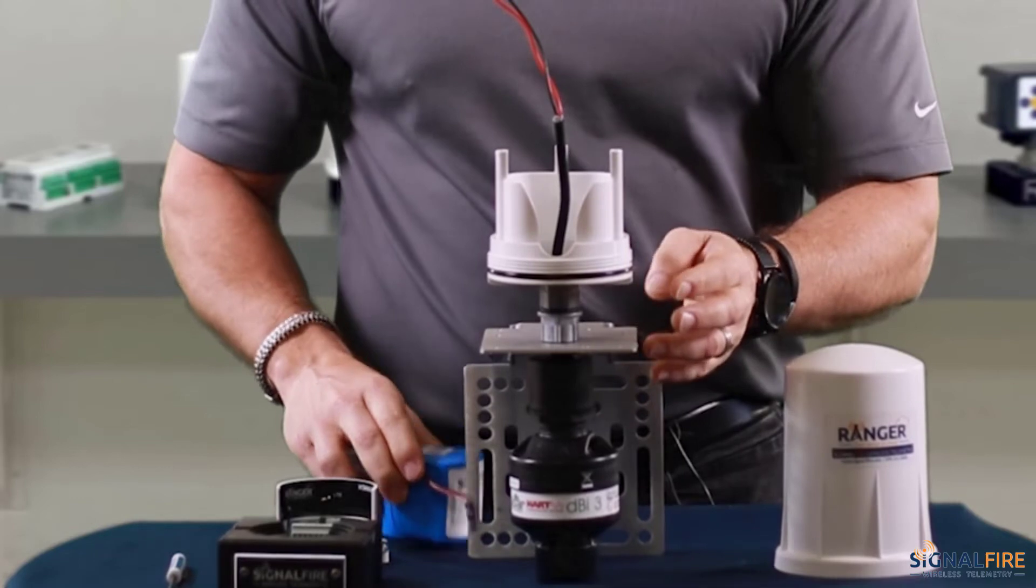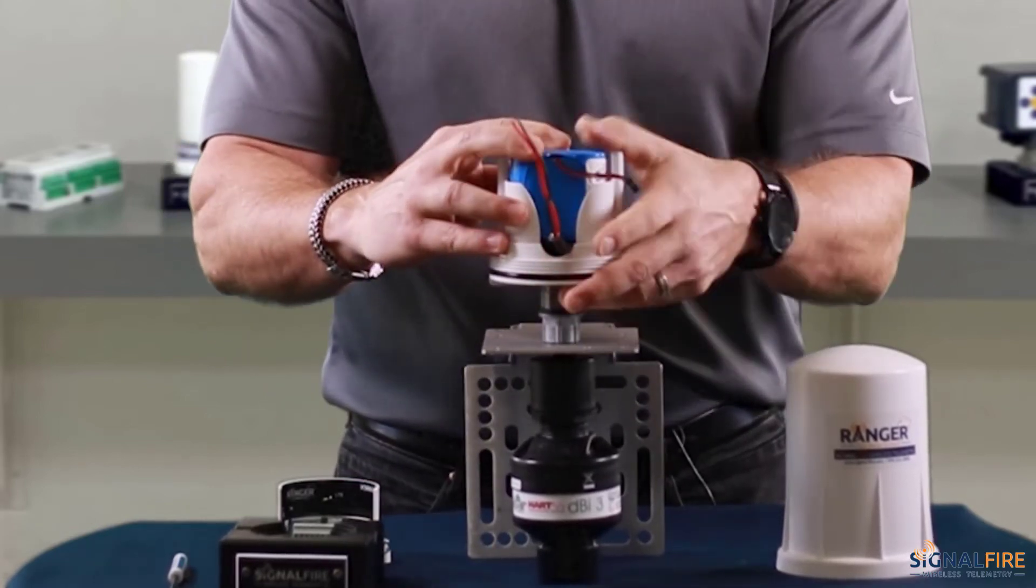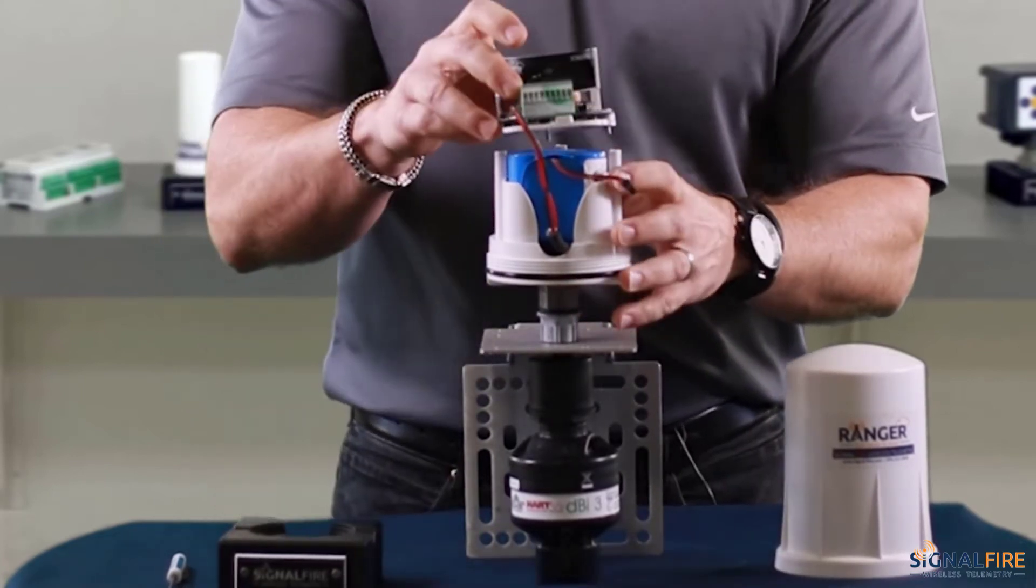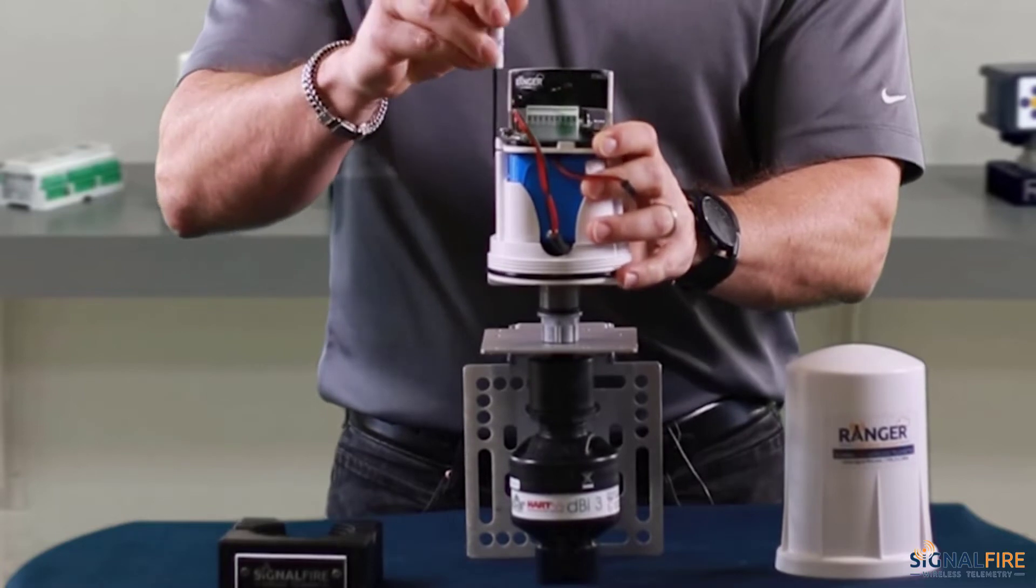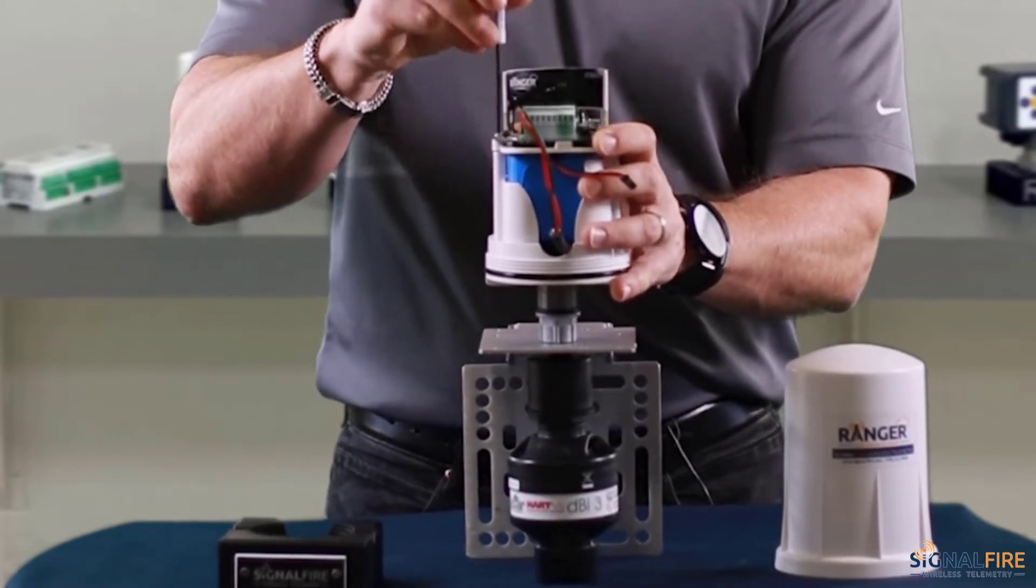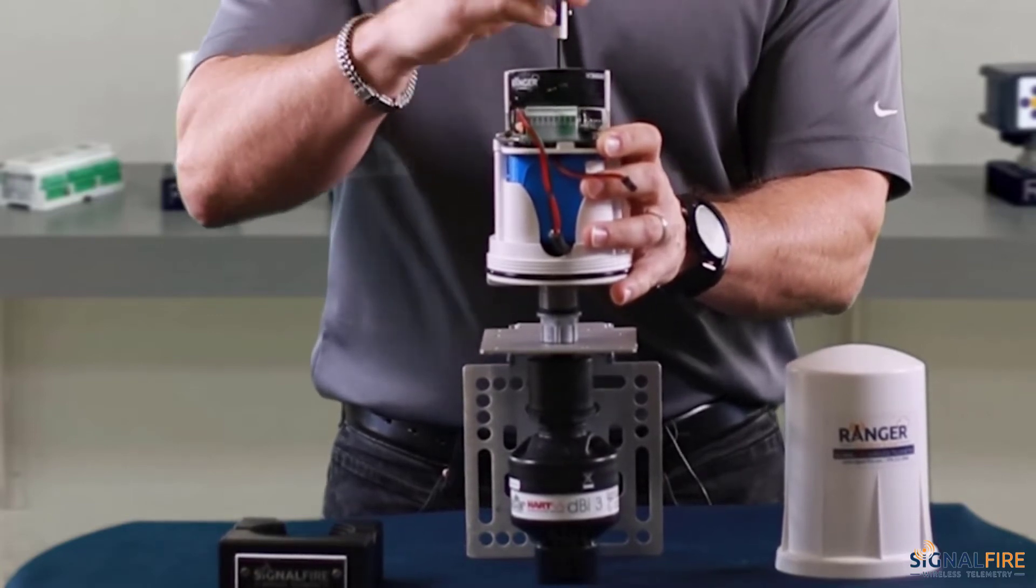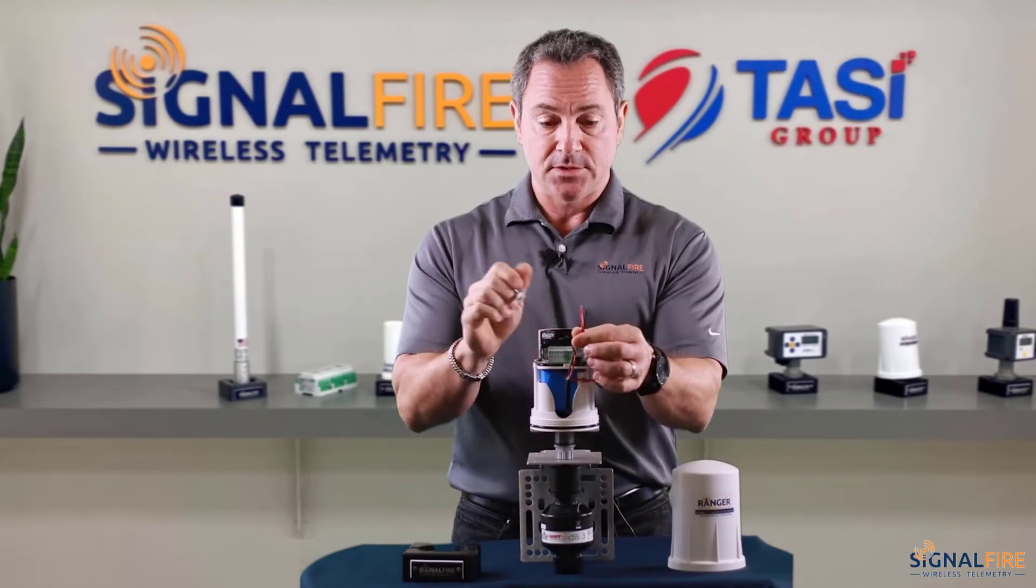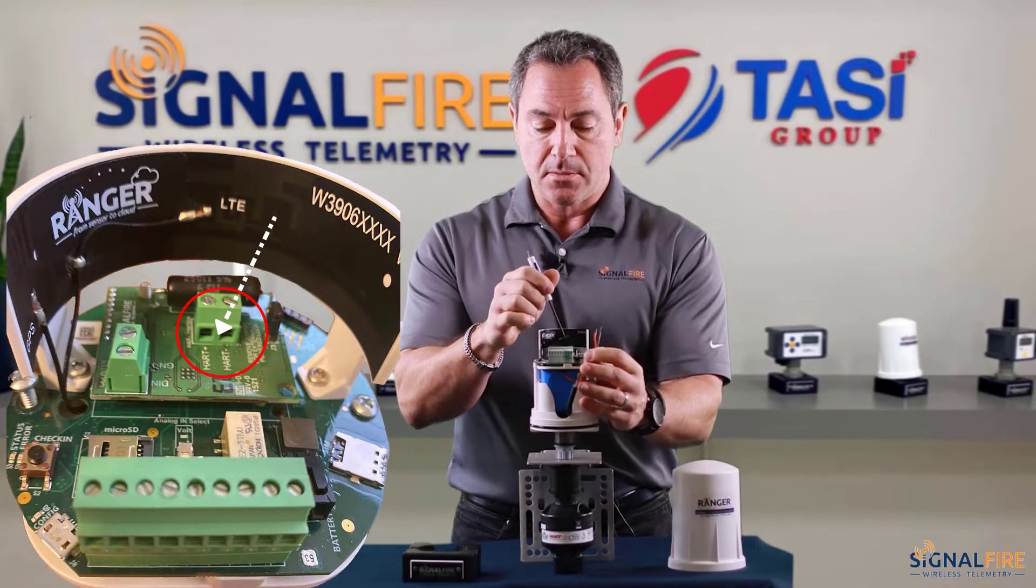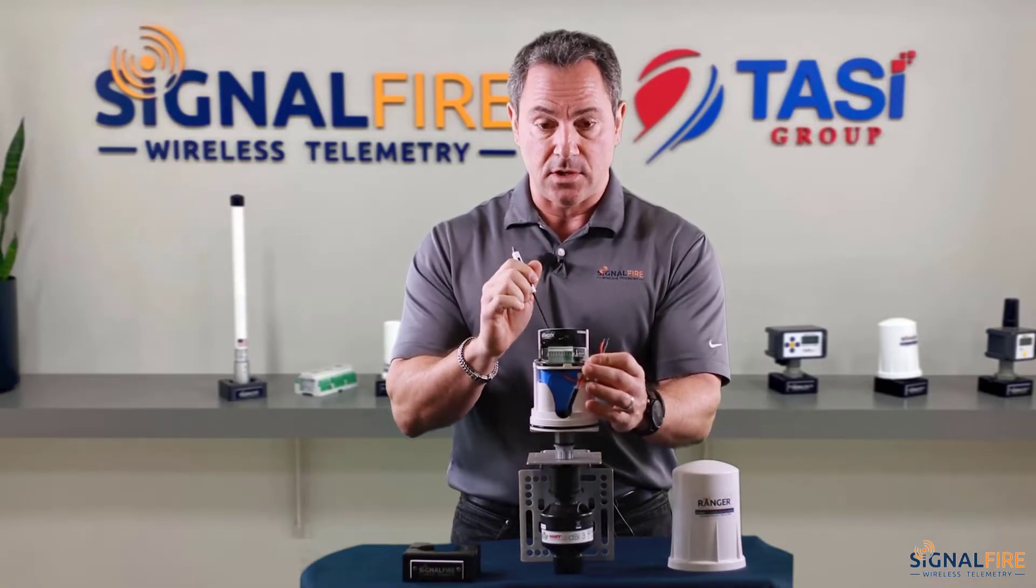And finally, let's reassemble the tower, put everything on top of it. Let's put the battery, then let's put the electronic module. We will secure the circuit board to the Ranger. And lastly, land those two wires, the positive and negative to the HART plus and minus terminals that you'll find on the daughter card.